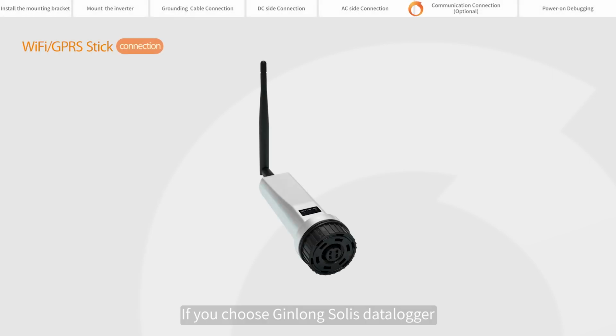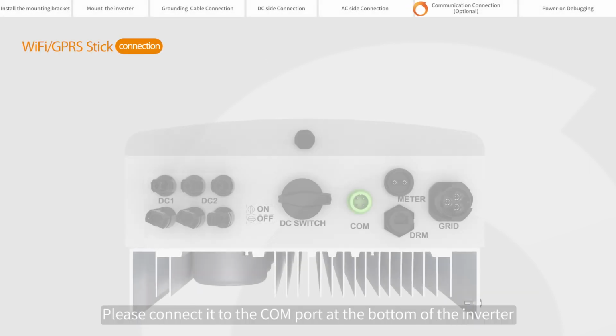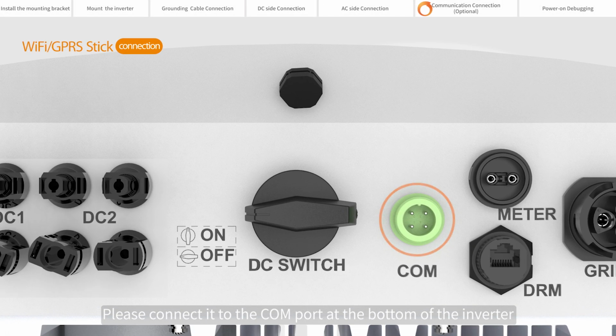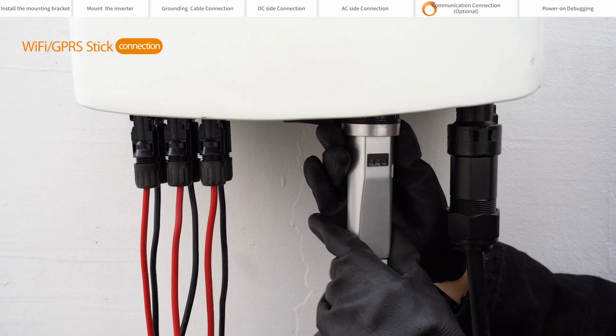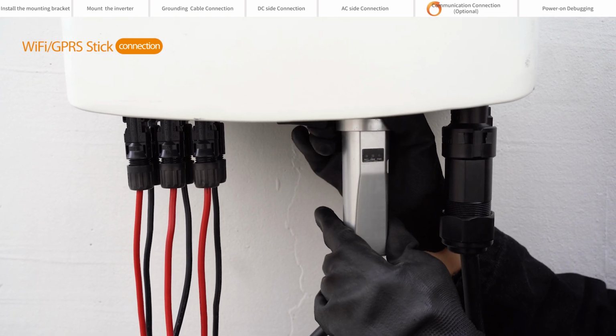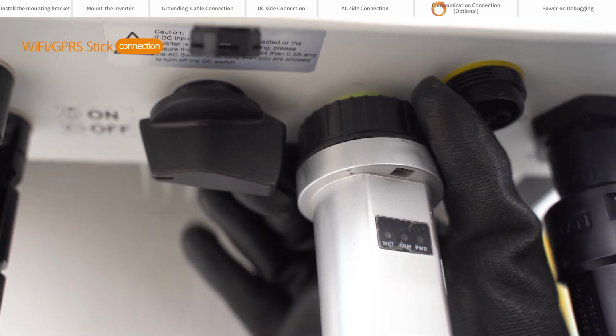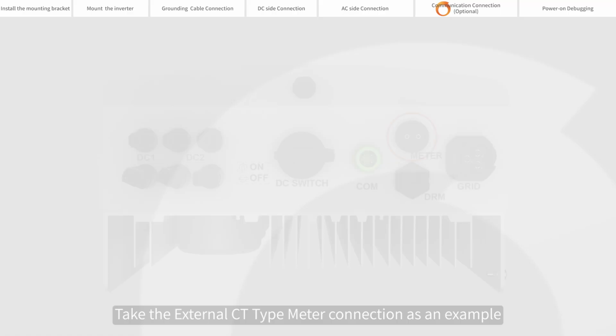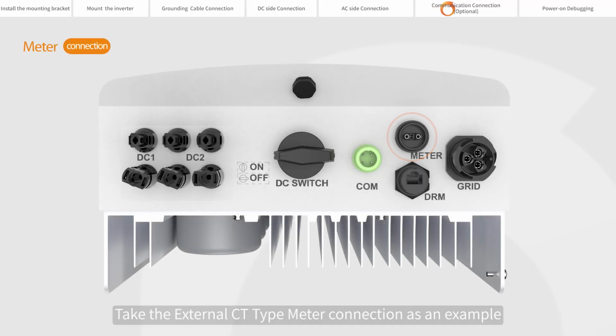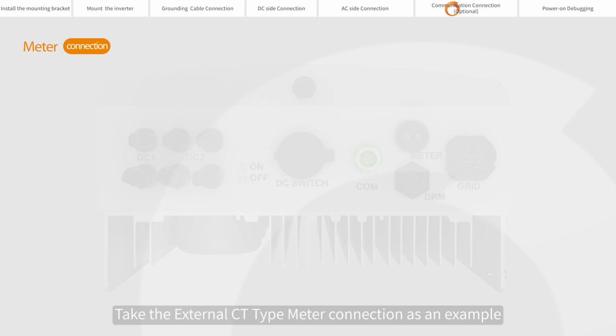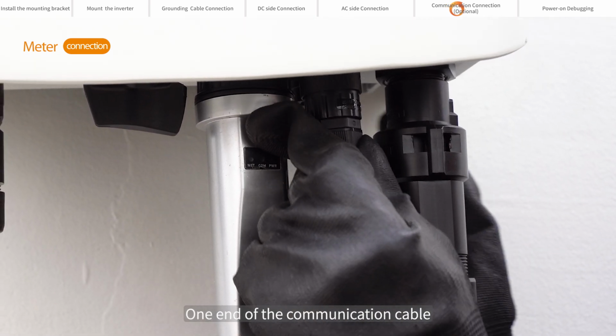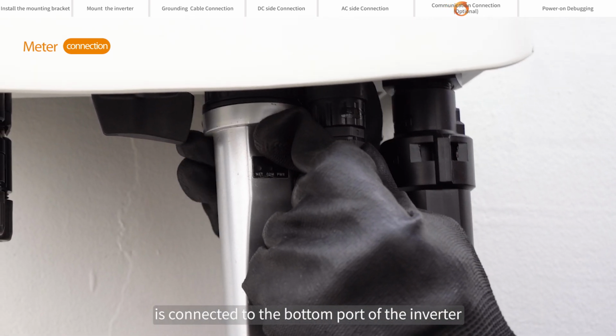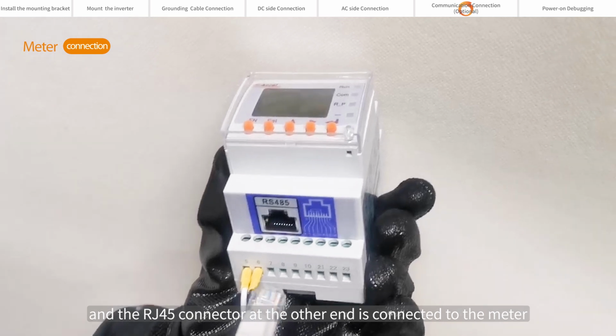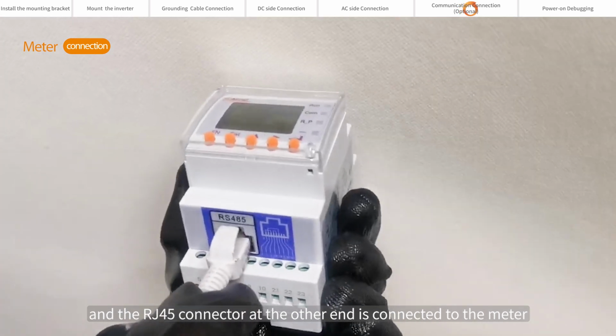If you choose a Solis data logger, please connect it to the COM port at the bottom of the inverter. Take the external CT type meter connection as an example. One end of the communication cable is connected to the bottom port of the inverter, and the RJ45 connector at the other end is connected to the meter.